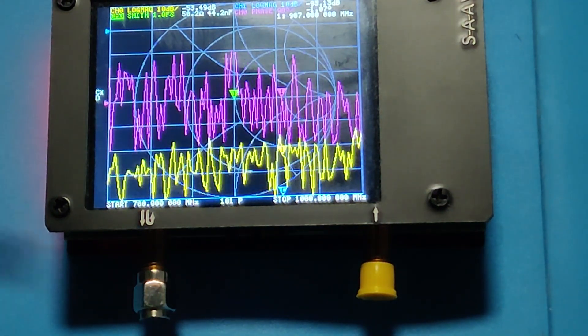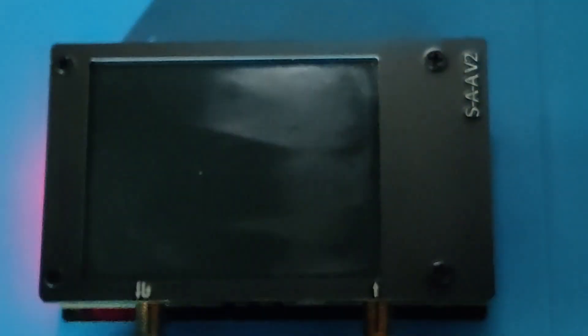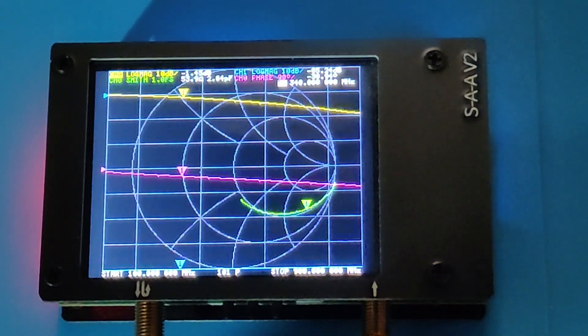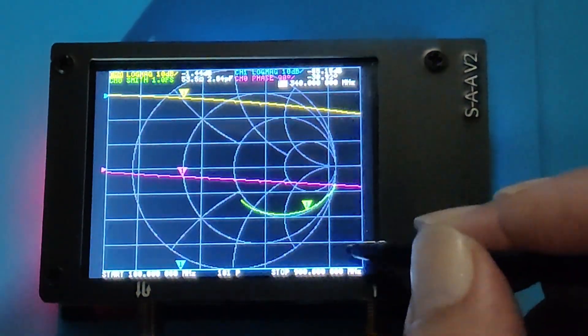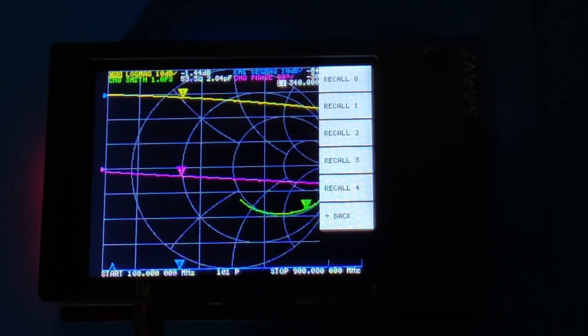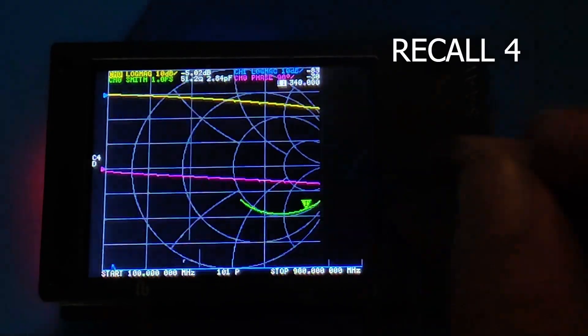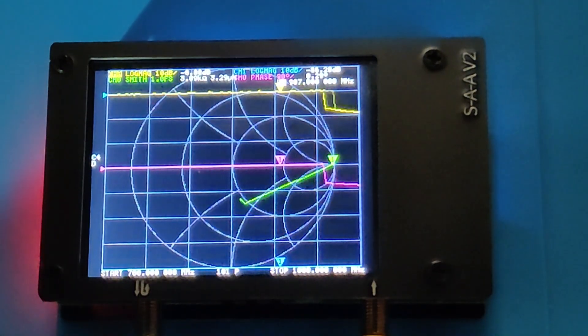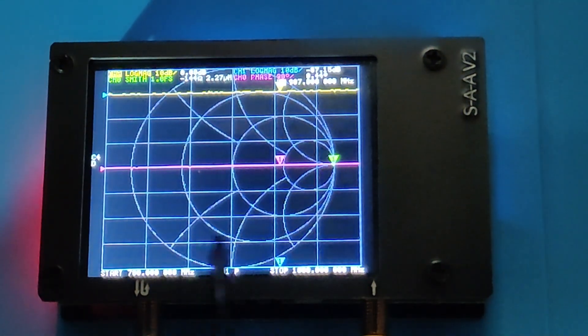I am doing an optional step to verify the calibration. We can do it anytime. I have just switched off and then switched on the device to open the menu, then clicked on recall and clicked on recall 4. This was the memory location where I stored my calibration.